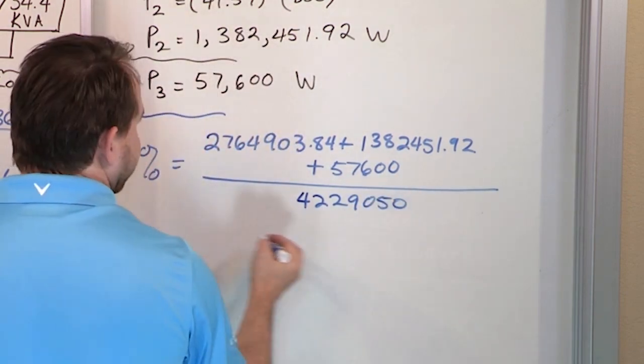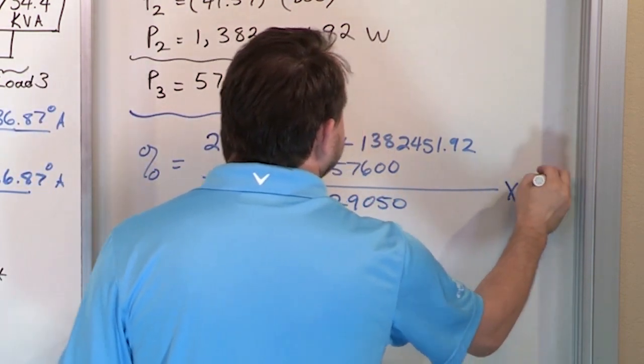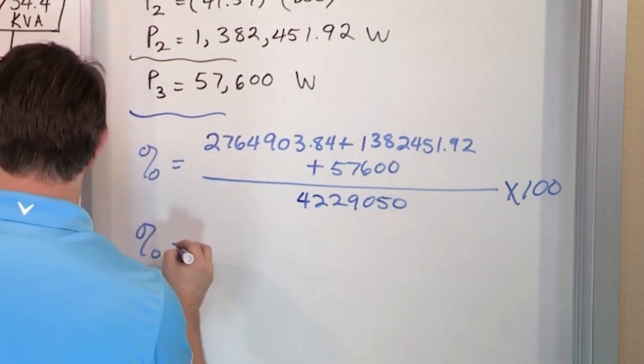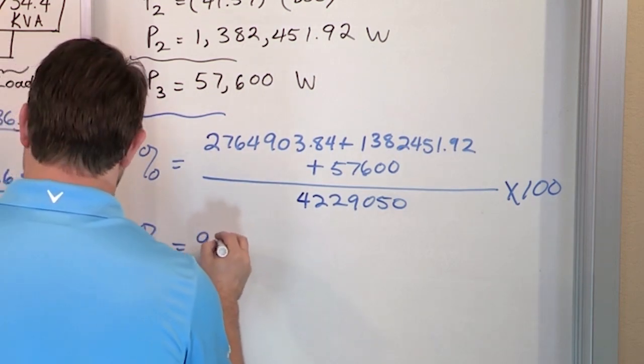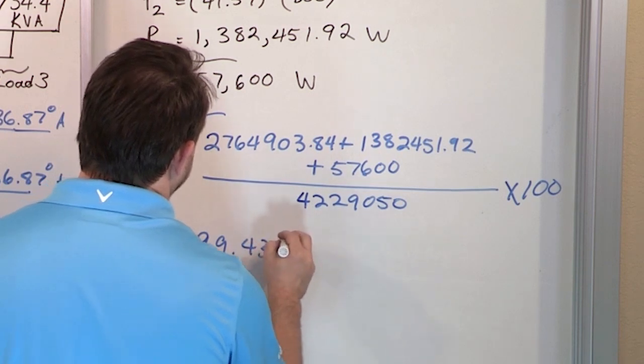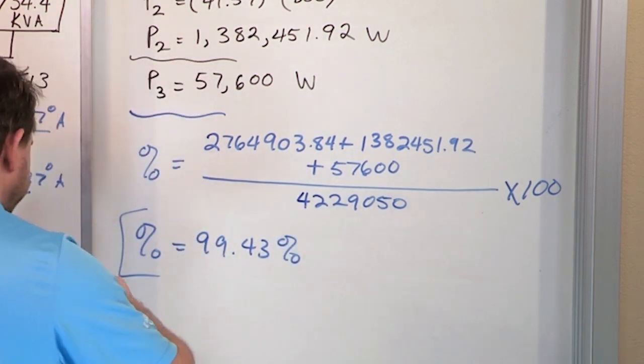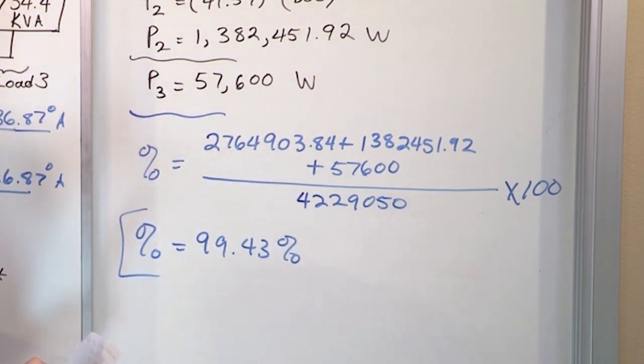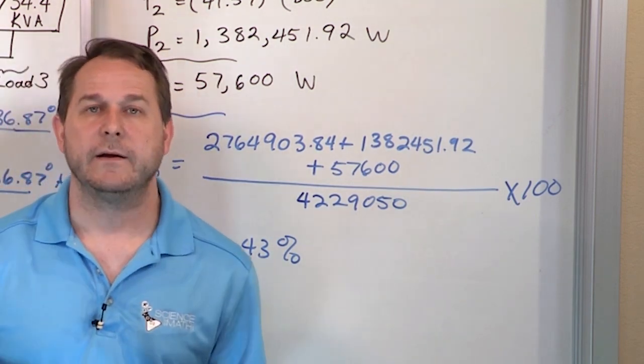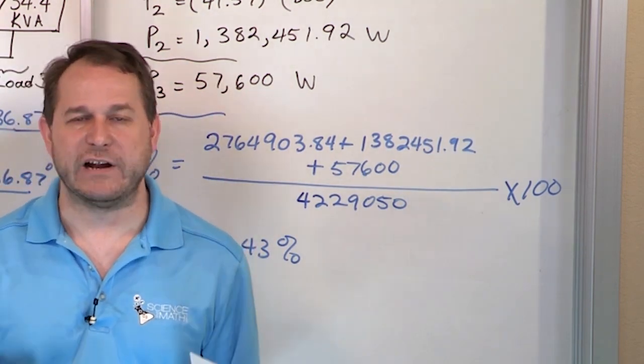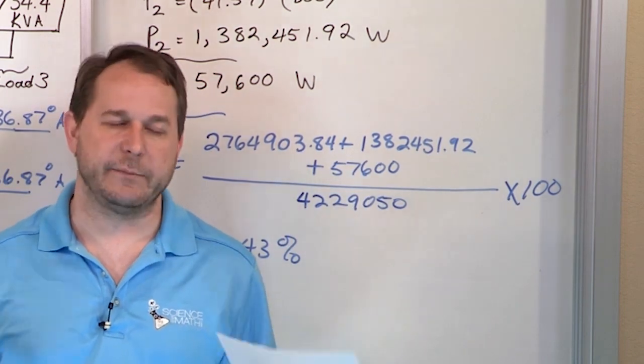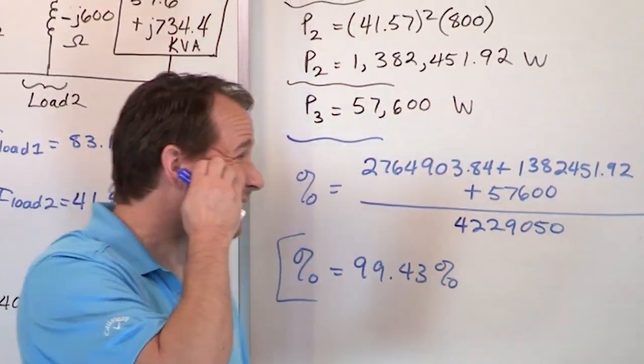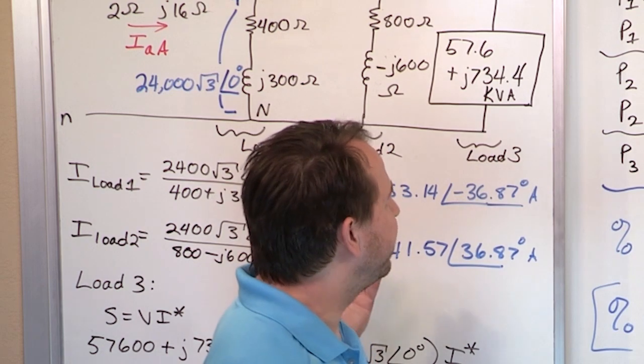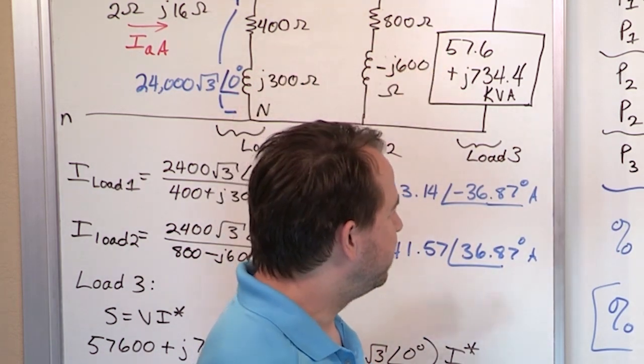So I'm just going to use that answer, 4,229,050. Multiplying the ratio by 100 gives a percentage of 99.43%, which is what you'd expect, since most of the power should make it to the load, otherwise you've done a poor job engineering the system, and should have lower resistance or impedance in the lines. So the trick to this problem, as with part A, was getting the single-phase equivalent down.